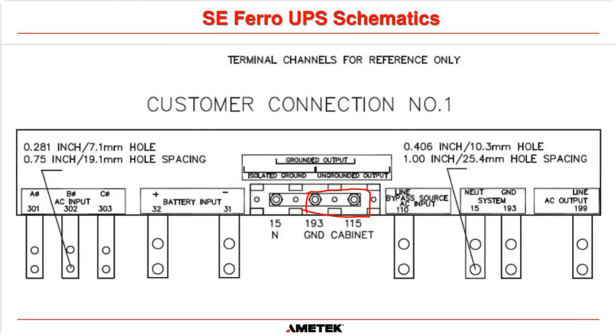So you would usually just have this bus bar connected, because in truth, if you know anything about separately derived sources and UPS supply in general, you're only supposed to connect a neutral to ground at one point, and that is the point closest to the supplying power. In other words, closest to the transformer that is supplying power to the system.